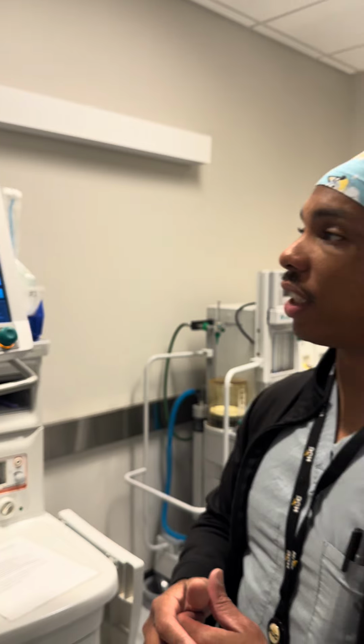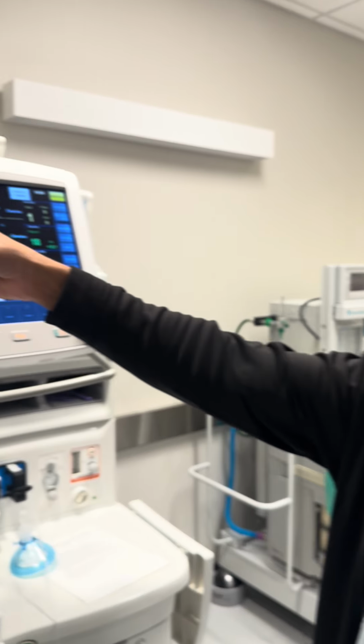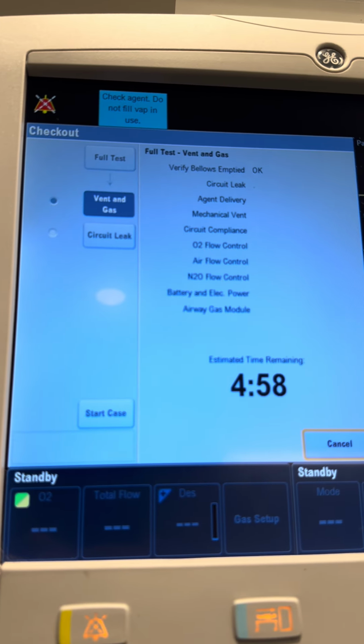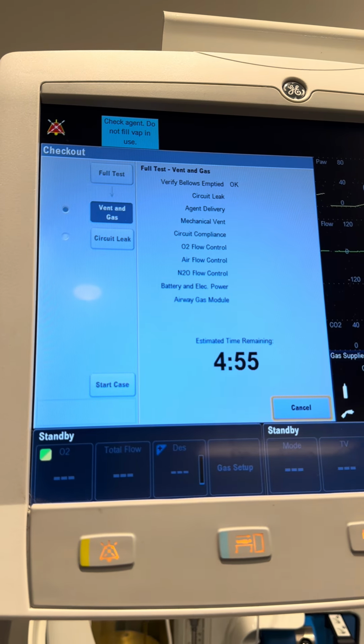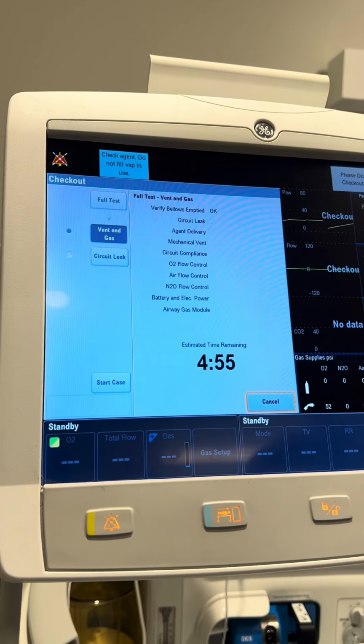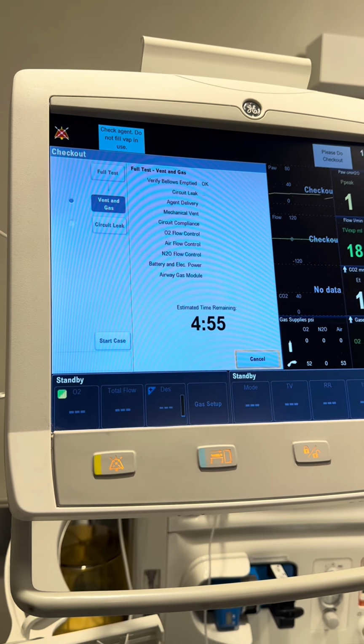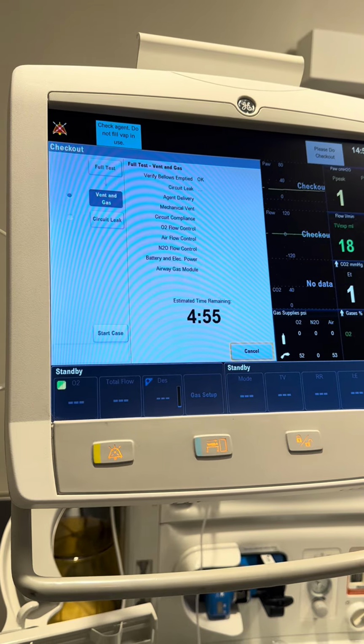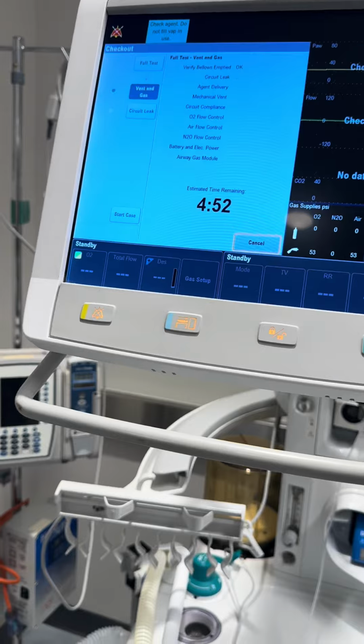Now with the test here, the full test, it encompasses the vent and gas and the circuit leak. You can do these individually, but usually in most facilities, we're either gonna do the full test or we're only gonna do the circuit leak, because the vent and gas is only when there's a low pressure leak, so we won't worry about that. The only ones I want you guys to worry about and focus on are full test.